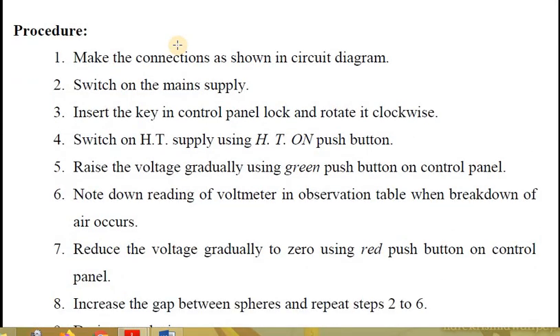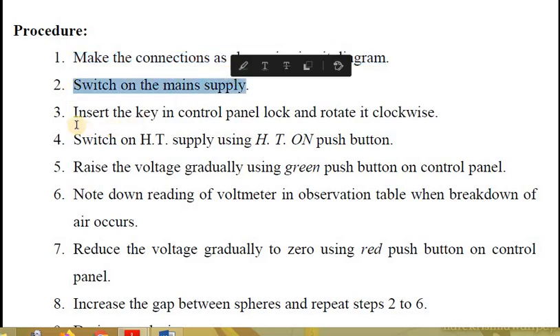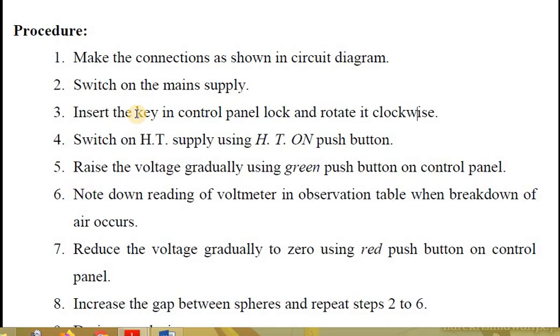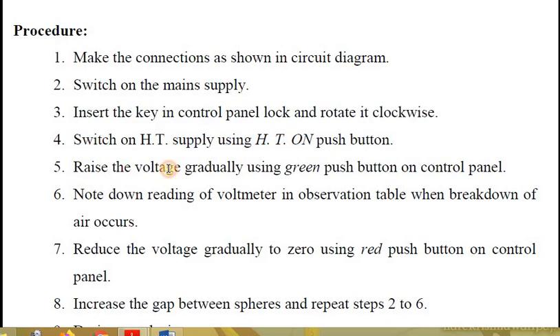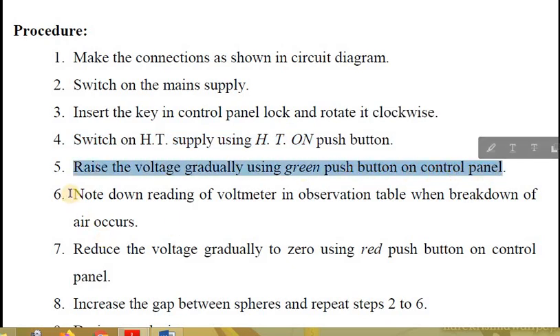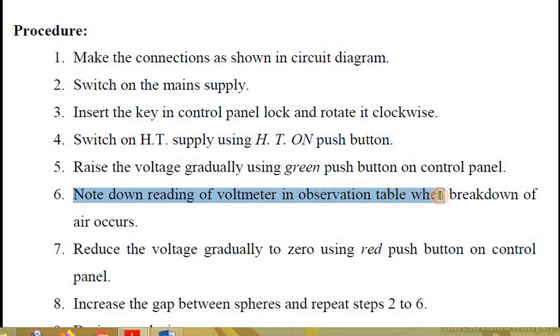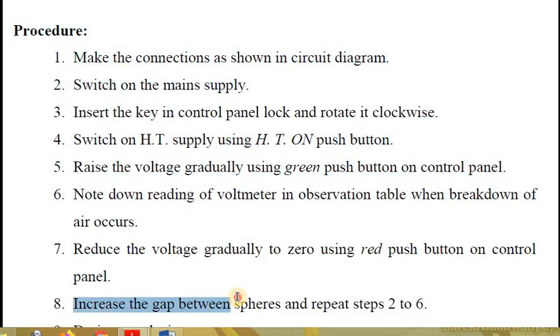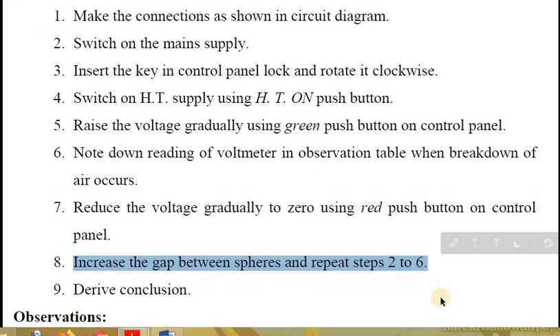The procedure is very simple. Make the connections as shown in the circuit diagram. Switch on the main supply. Insert the key in the control panel and rotate it clockwise, as it is a high voltage equipment — the company has provided a key which must be inserted and rotated clockwise to activate the panel. Switch on the HV supply using the HV on push button. Raise the voltage gradually using the green push button on the control panel, and note down the reading of the voltmeter in the observation table when breakdown of the air occurs. Reduce the voltage gradually to zero using the red push button on the control panel.